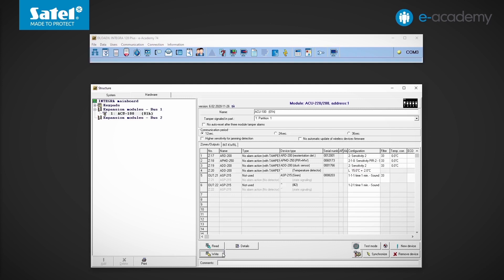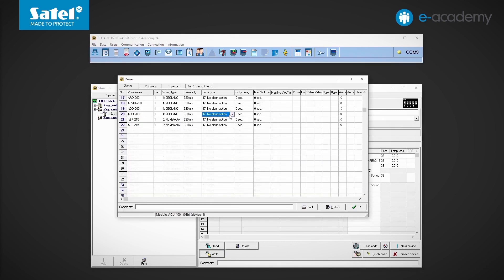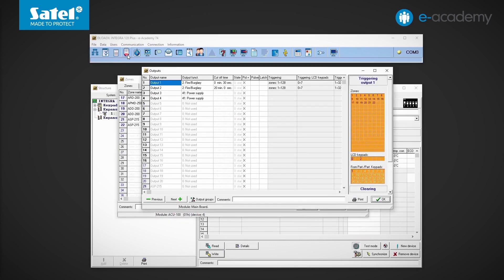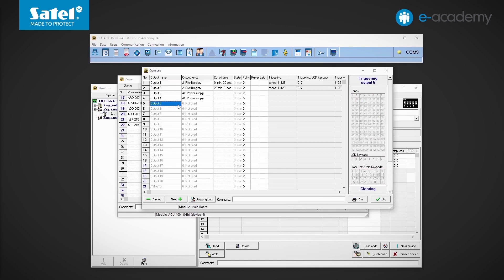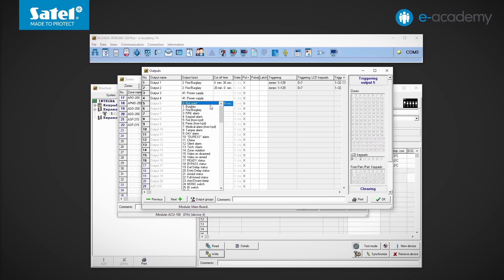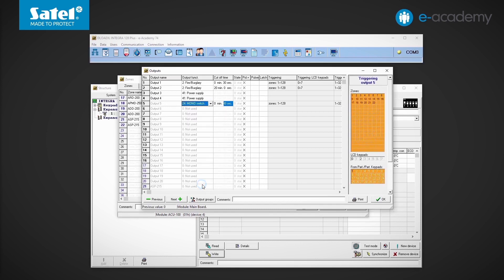Zone 20, to which the temperature detector is assigned, is set to response type number 47, i.e. no alarm action. I am now going to the list of outputs. I select output number 5. If you want it to be activated when the temperature falls below a preset threshold, you can select output type number 24, mono switch with no cutoff time.